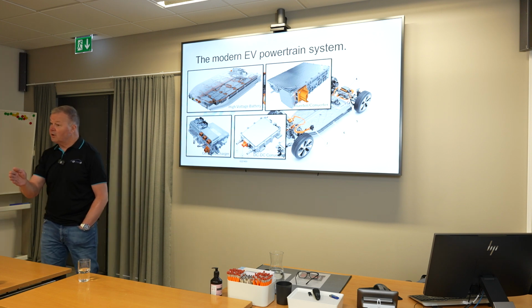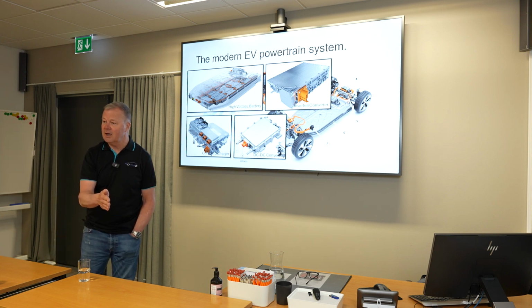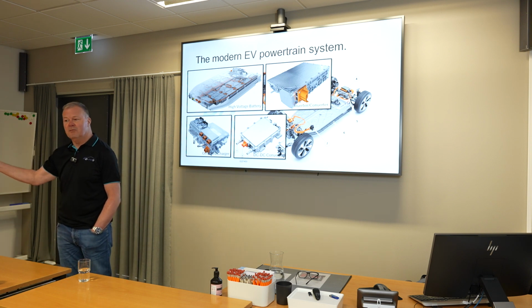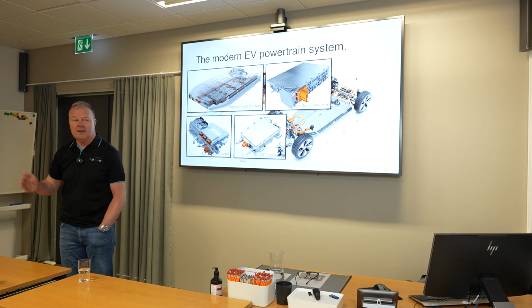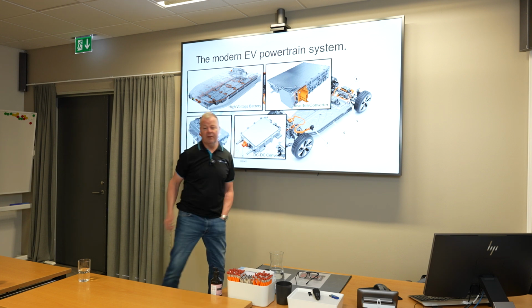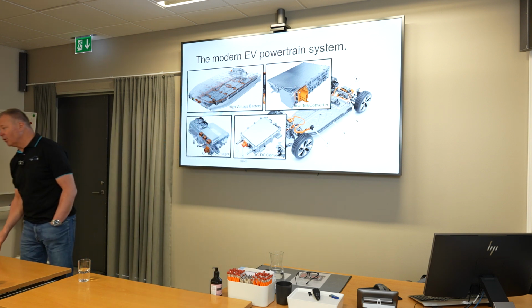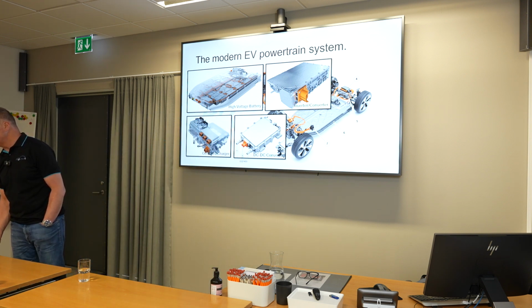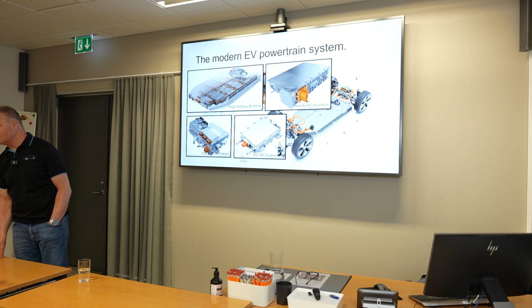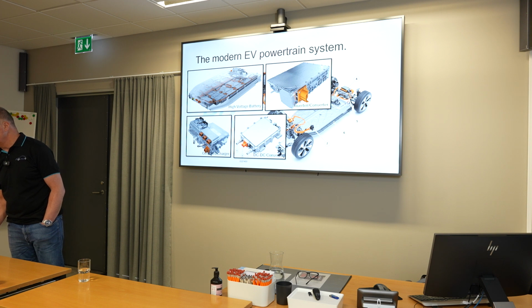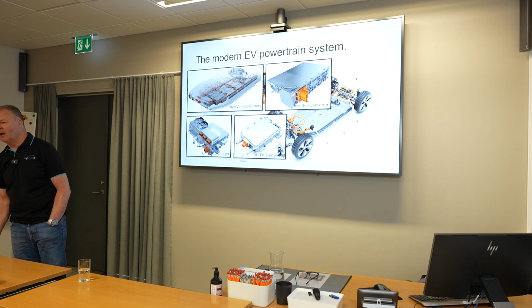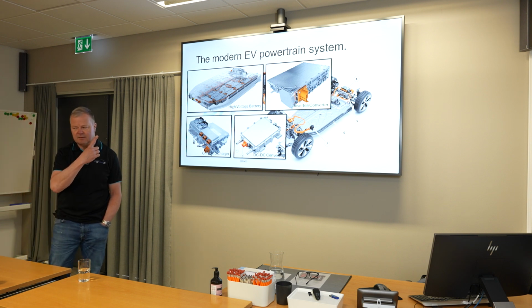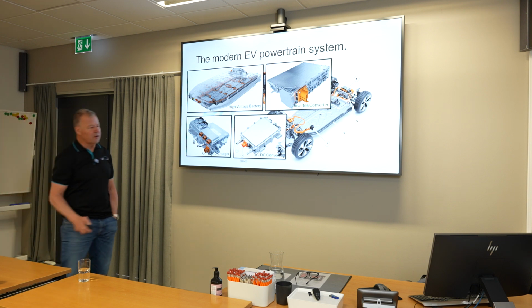So we can develop torque at 0 RPM, and we can have it running at maximum RPM with 0 torque if you want. The inverter-converter, in reality, is your gearbox, because it can vary the torque and increase or decrease the speed, and increase the torque wherever it likes. So that's where your efficiency comes from. Interesting stuff, this.